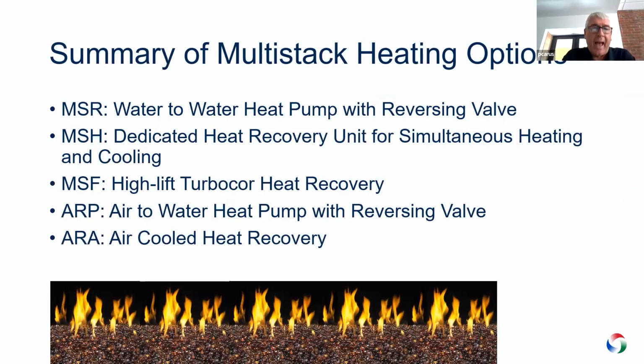What do we do? What do we have that can help you with your solutions? We have 4 or 5 different product lines. One of them is just a straight traditional water-to-water heat pump using a reversing valve. We'll talk about each of them in more detail. Another one is a dedicated heat recovery chiller, which will do both heating and cooling and simultaneous activities. A more recent addition, and by recent I say within the last couple of years, is what we call an MSF. We use Turbocor's new high lift heat recovery compressor in that application to do both heating and cooling.